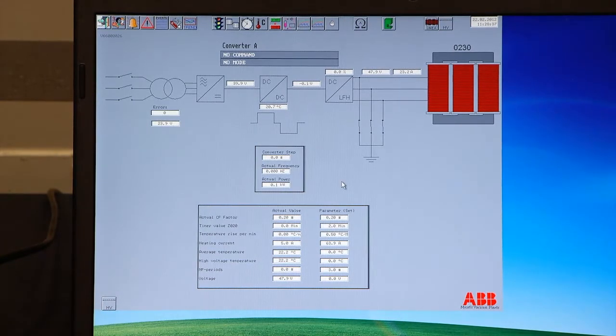And that happened because it did a resistance measurement on each leg. Yes, because of the high voltage measurement, because you're saturating one leg. Yeah. And if this is not performed, you will have a very unbalanced resistance reading the next time you do the resistance reading. So now it's balancing all 3. It's balancing everything up, ramping up the voltage and ramping down the voltage. That's done automatically. Okay, no command, no mode, main contactor is open, grounding switch is closed.